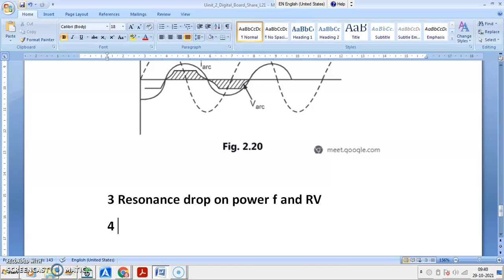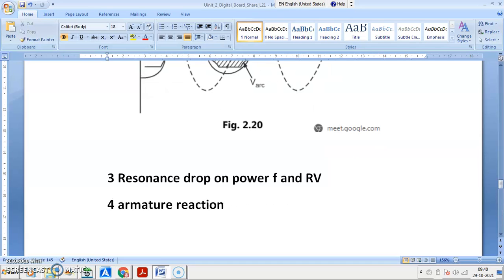Then armature reaction in case of motor. In case of motor, armature reaction may also cause an effect on arc quenching. When a short circuit takes place, when short circuit currents are there at very low lagging power factor, they will produce demagnetizing effect of armature reaction. Therefore EMF decreases under short circuit condition. Therefore EMF requires some time to regain the original value, and then the power frequency of recovery voltage is less than the normal system voltage. This will also affect the current interruption.